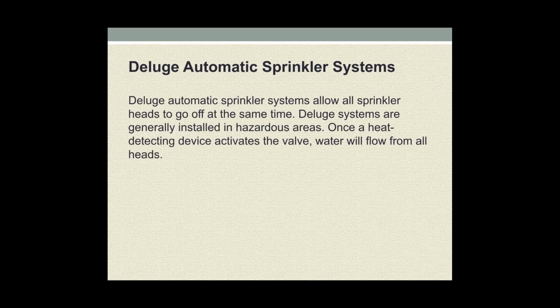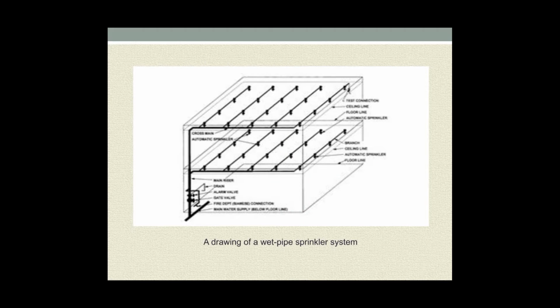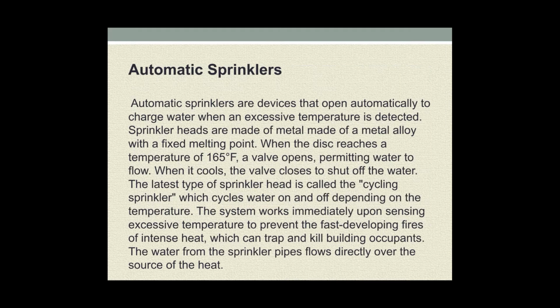The deluge automatic sprinkler system. The deluge automatic sprinkler system allows all sprinkler heads to go off at the same time. The deluge systems are generally installed in hazardous areas. Once a heat detecting device activates the valve, water will flow from all heads. A drawing of a wet pipe sprinkler system. This is their example.